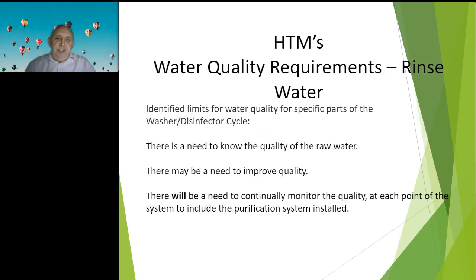So in the HTM, there are dedicated water quality requirements for washer disinfector applications. There are identified limits for each particular water quality parameter. It's very important to know what sort of water quality we have at source. We may need to improve the water quality because we may have certain parameters that we don't want. And there will be a need to continually monitor the quality. We don't just commission equipment and water quality is as it is at point 1. We need to monitor at periodic frequencies, to make sure the source is consistent, to make sure any purification system that we have installed is working correctly.